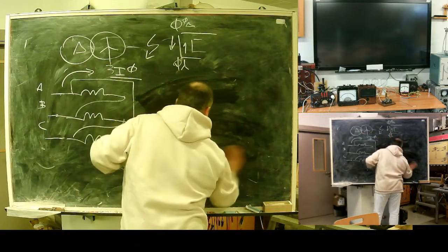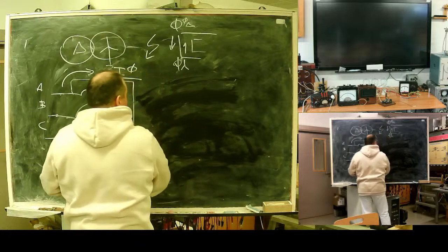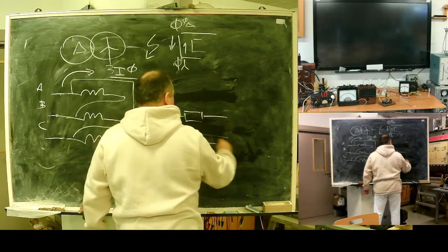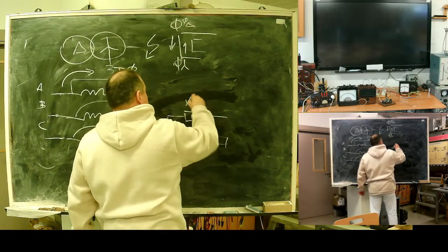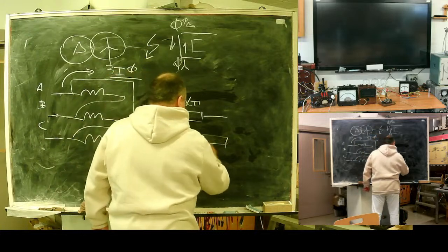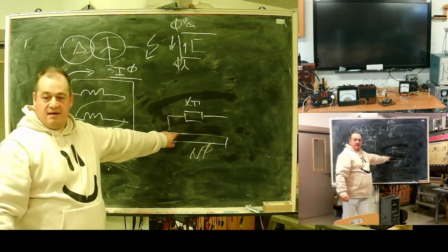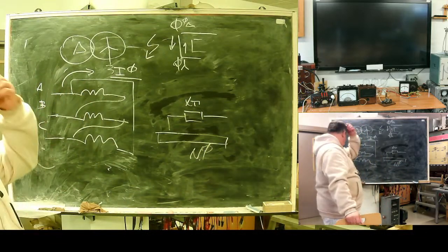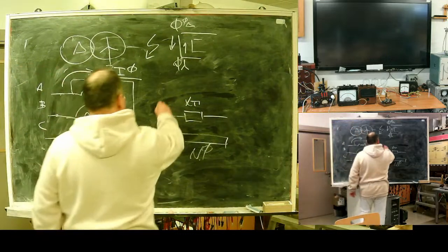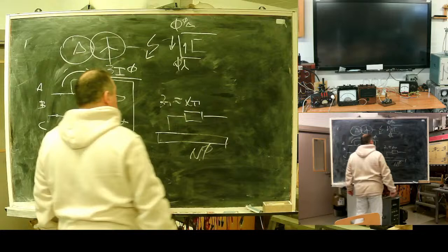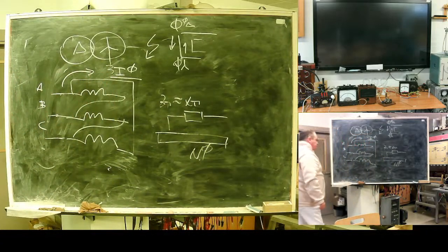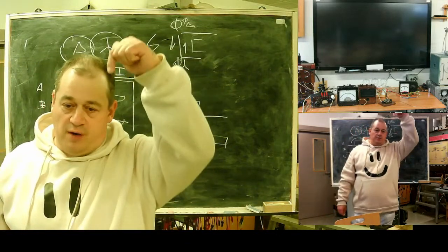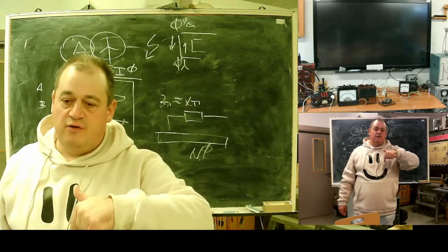And in our schematic, the transformer will appear as a transformer reactance connected to the common wire of zero sequence. Zero delta windings form a drain or sink for zero sequence.